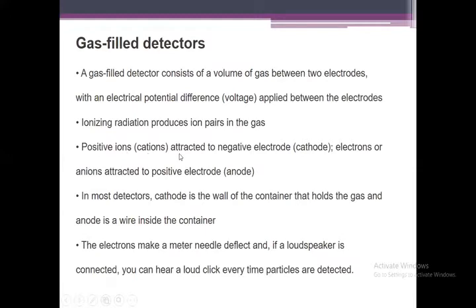Positive ions are attracted to the negative electrode and electrons are attracted to the positive electrode. In most detectors, the cathode is the wall of the container that holds the gas and the anode is the wire inside the container. The electrons make a meter needle deflect, and if a loudspeaker is connected you can hear a loud click every time particles are detected. When a particle is detected by the system, that is known as one pulse.